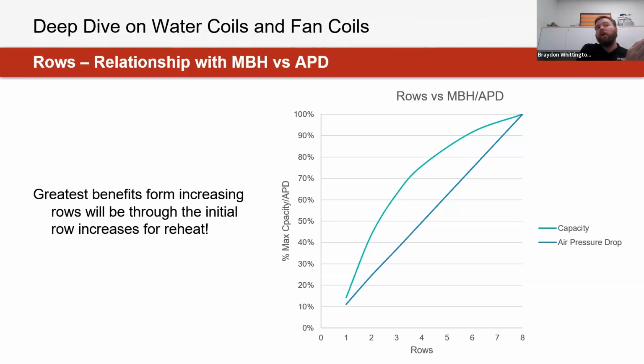So in a lot of cases, working with single duct VAVs or lower rows of coils, the most significant increase in capacity that we're typically going to see is for those first few rows of coil that we add to our system. So something to take into consideration: say maybe you initially have it spec'd out with a 1-row cooling coil for a product, and then they're asking to achieve a certain capacity benchmark. Before jumping to a 6-row or 8-row coil, it's more beneficial to look at the incremental step of some of the lower rows.